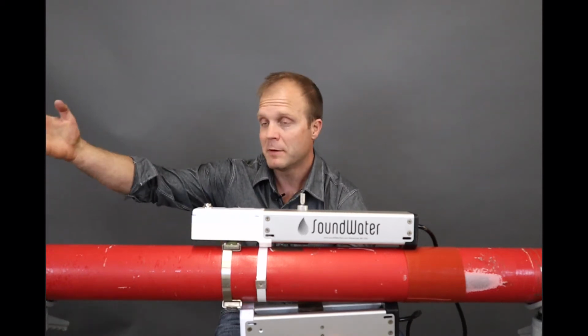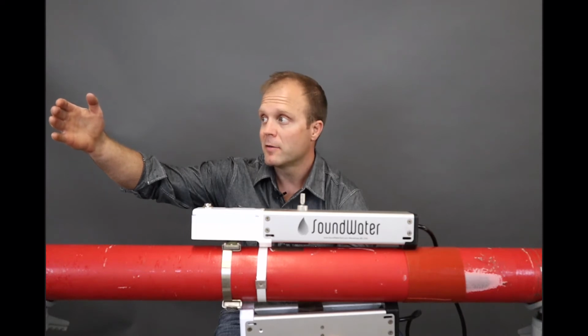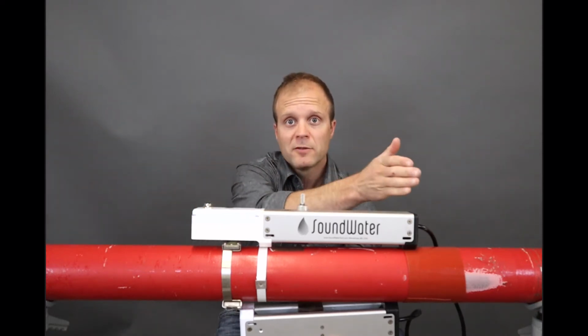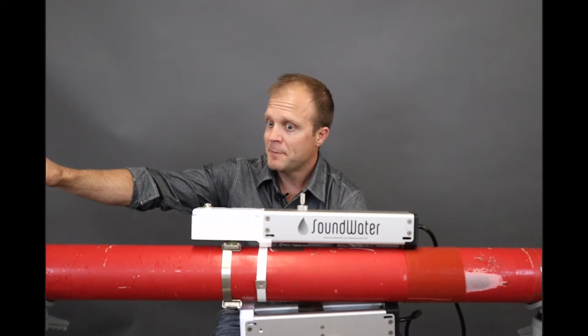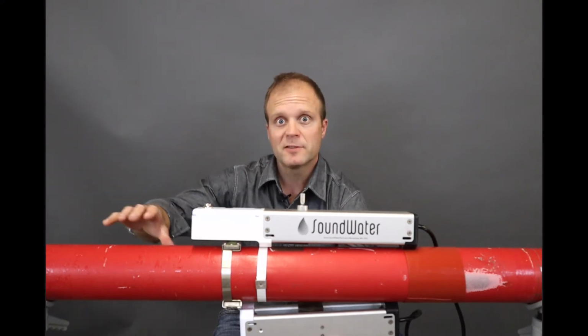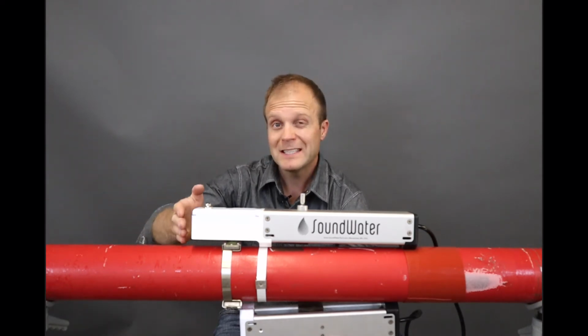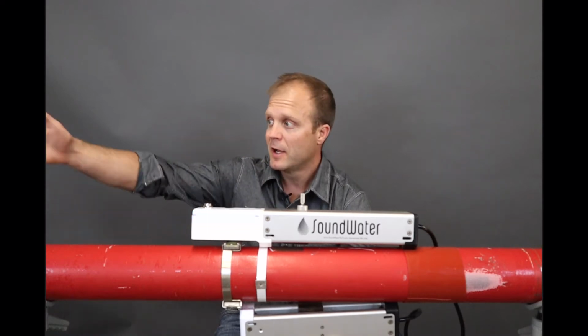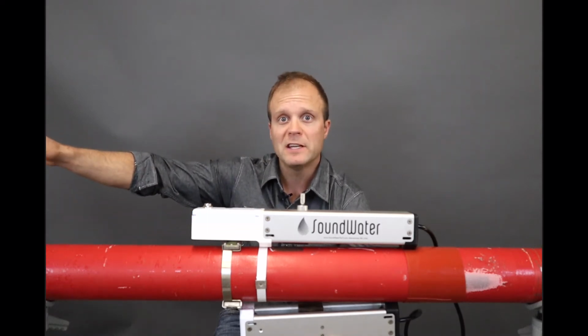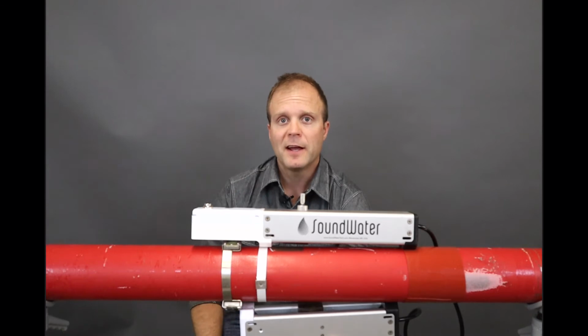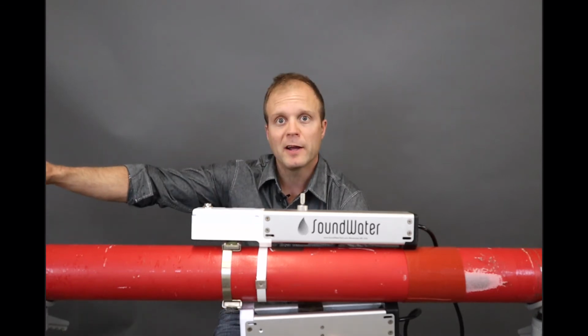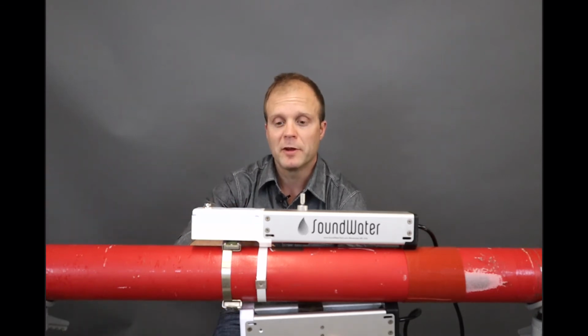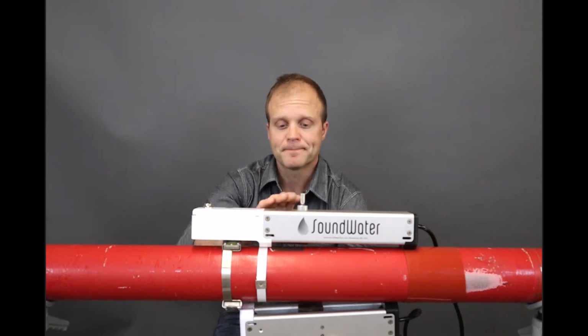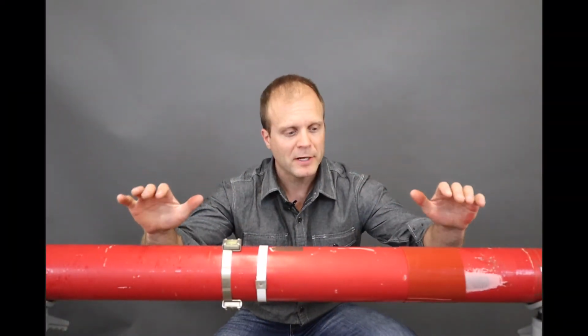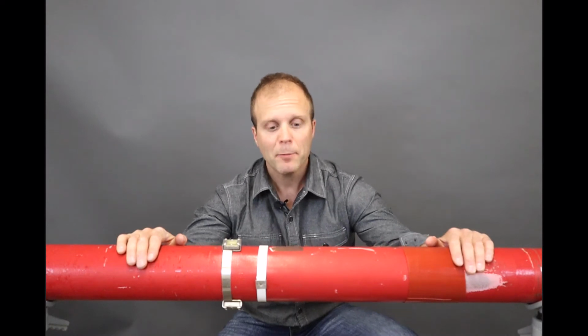So if the flow is coming from my right-hand side moving to the left, this is upstream, we would want 10 diameters. So this is a 3-inch pipe, so we would want at least 30 inches between the flow meter and any elbow or T or valve or something like that. And that just allows the fluid to stabilize before it hits the flow meter, and we can get a better measurement.